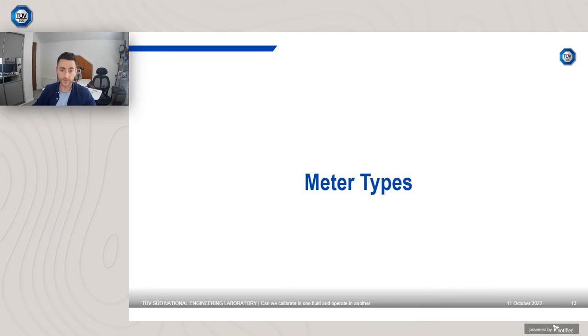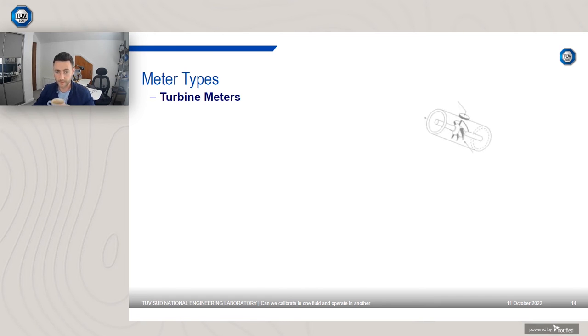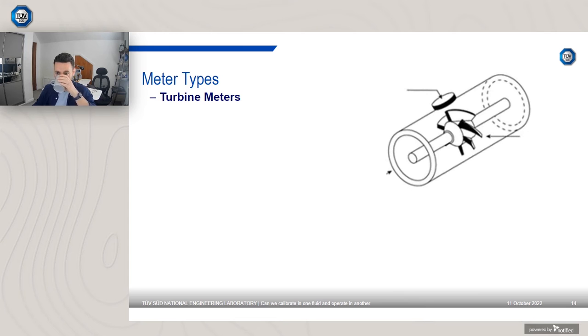So before we go into too much detail, it's worth discussing the actual meter types we're talking about here, because not all flow meters can be calibrated in one fluid and used in another, simply due to their design characteristics. So in terms of meter types, I have turbine meters here, a fairly common flow meter. I'm sure most people are aware of how a turbine meter operates, so I won't go into too much detail. As the flow passes across the turbine, spinning the device, you've got a pickup that picks up the number of pulses via the rotations, which is proportional to the velocity. From that you can get the volumetric flow rate.